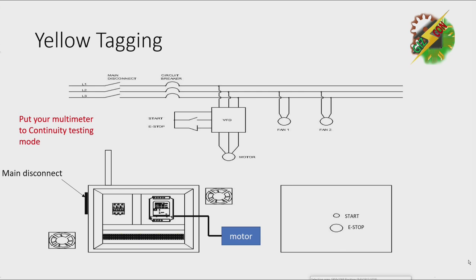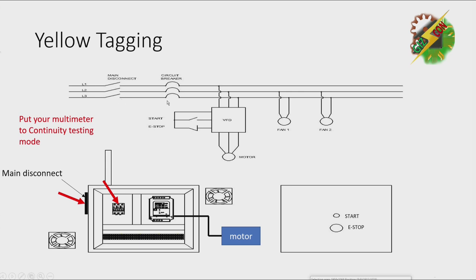First, you need to put your multimeter to continuity testing mode. Then put the lead of your multimeter to your main disconnect and to your circuit breaker. You need to check the wire here one by one. You need to check the continuity of each wire. And after you check, you can use a highlighter to mark the lines that you are already finished.